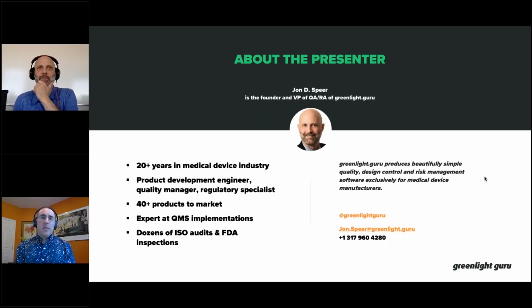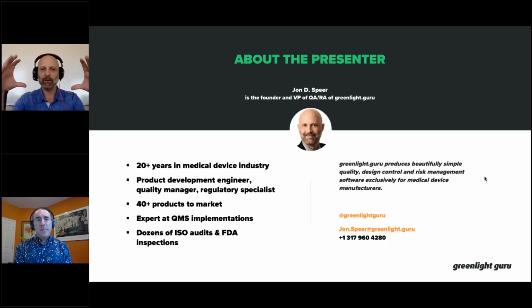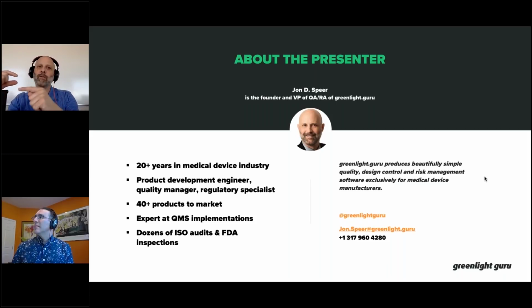Right. So the inputs describe the what, all the things that your product needs to do. If you broke it down, you have multi-level components in your design and development efforts. You may have your design control activities, and you define components or subsystems. So you have a section for electrical, another for mechanical, another for firmware, and so on. Within that subheading or subcomponent, you would define the specific design input requirements. Again, the what. What does that electrical system need to do?